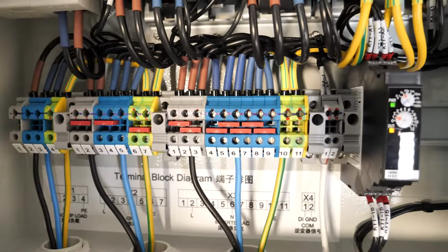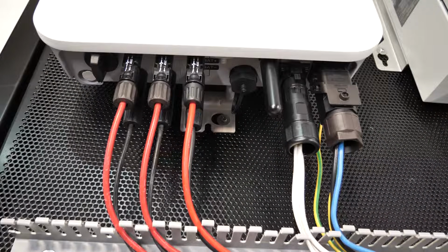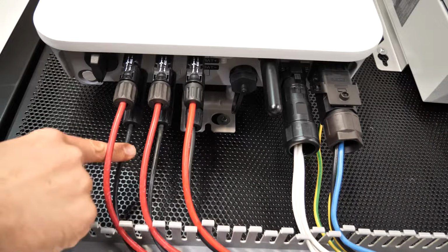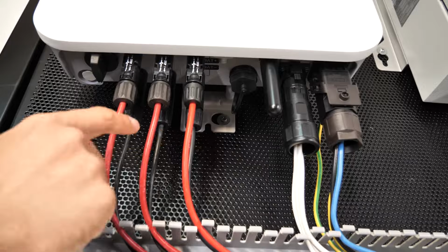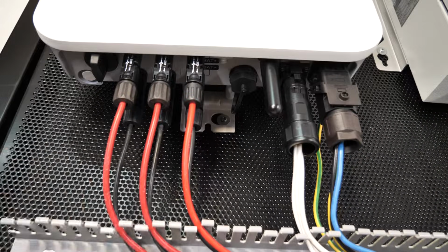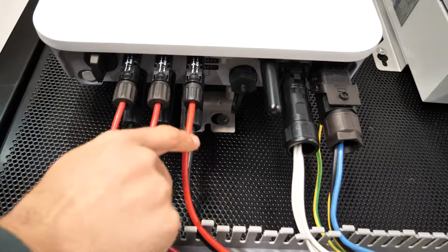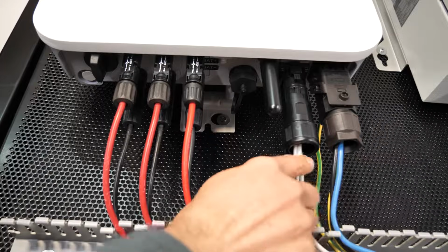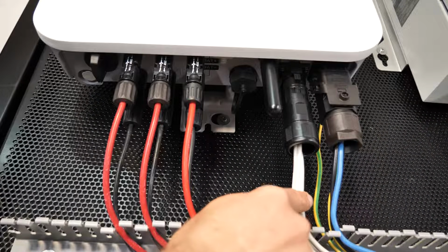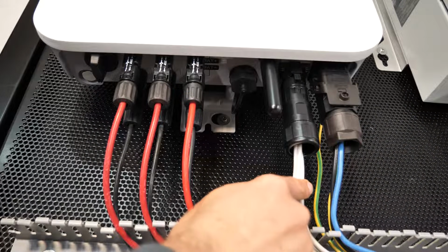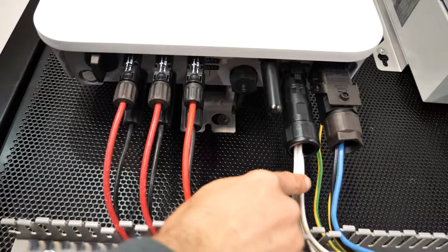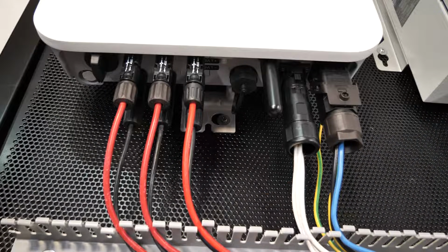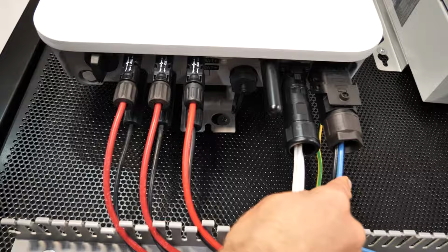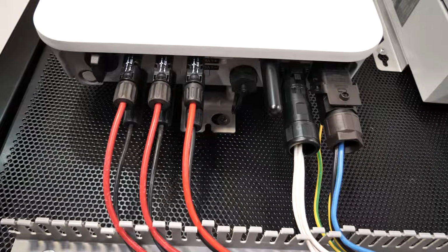Here you can see in more detail the connections of the photovoltaic inverter. We have the positive and negative towards the first series of panels, positive and negative towards the second series of photovoltaic panels, and the positive and negative towards the battery. The communication cables go to the battery, to the energy meter, and to the contactor box. Here we have the alternating current connections and the ground cable that goes towards the chassis of the photovoltaic inverter.